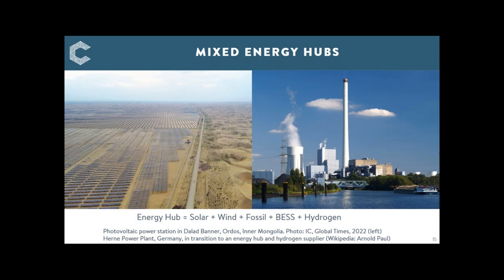The renewable section has a capacity of around 12 gigawatts, mostly solar power, with wind around 4 gigawatt capacity, while the coal station is sized around 4 gigawatts. So on an average basis, the coal station will provide about half the power. This is aimed at ensuring dispatchable power, using storage to maximize the benefit of renewables, but also to reduce the operational duress of the fossil plant operation, as we know these have been starting to cycle quite severely to cope with variation in renewable power.